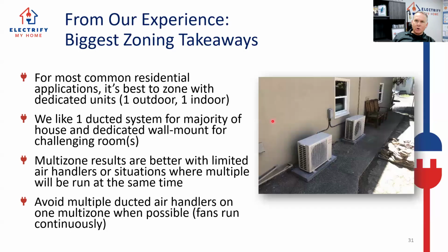Biggest zoning takeaways. For most common residential applications, it's best to do a zone with two one-on-one ducted units if you can. We've got a lot of systems out there that are two-zone multi-zone, and they've got a ducted system for the majority of the house, and maybe a second wall mount unit in a basement room where it's less critical. Or like that room over the garage that never cools off, that's fine with a multi-zone, because I'm taking care of most of the house with one zone and I'm just hitting a spot with the other. But one-on-ones are always better.